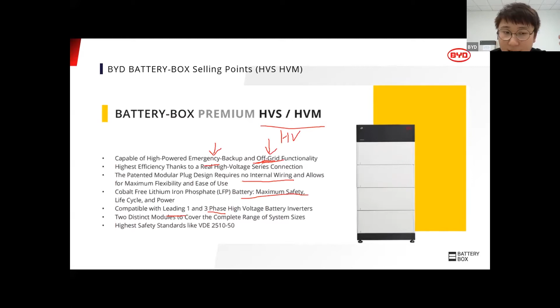All right, and most safety: no internal wiring, and it's a real high voltage series battery, which means no DC to DC converters, giving you the highest efficiencies. Each battery is 48 volts, this is for the HVM. The HVS is slightly different, but they are all connected in series, getting a voltage range between 200 volts and a maximum of 500 volts, just for example.